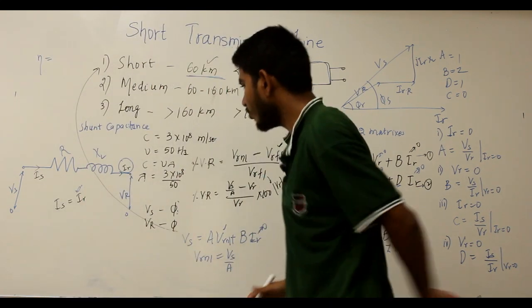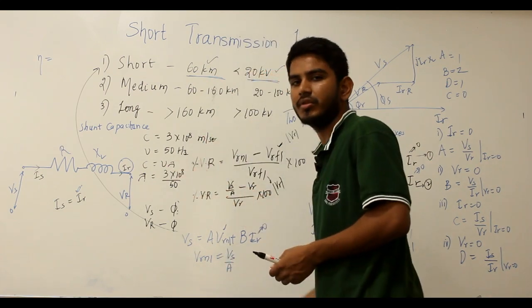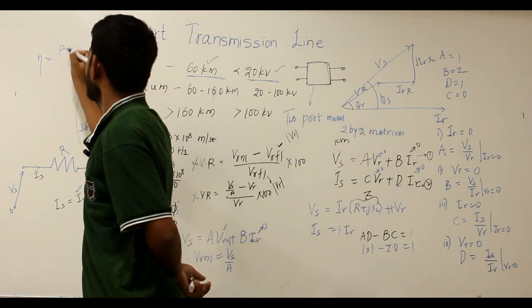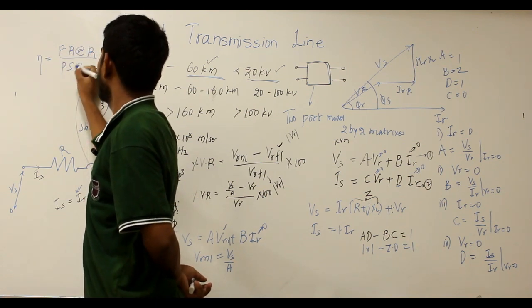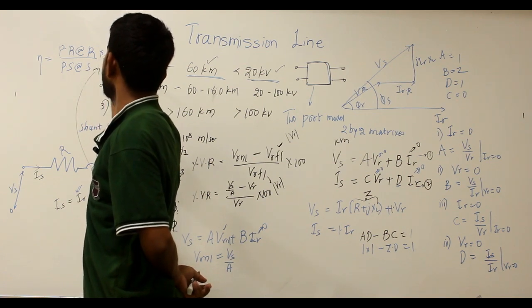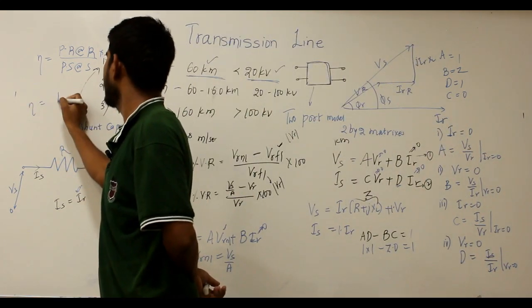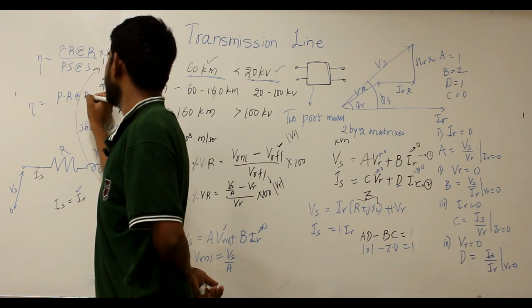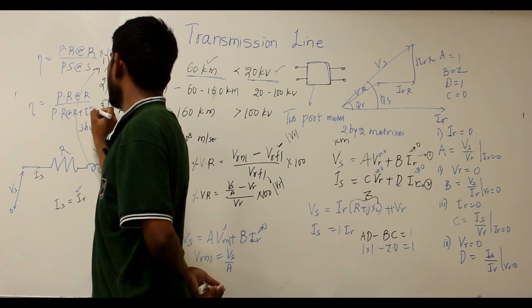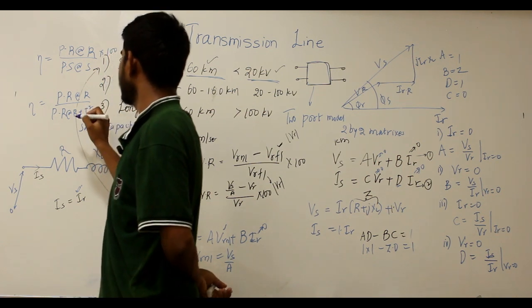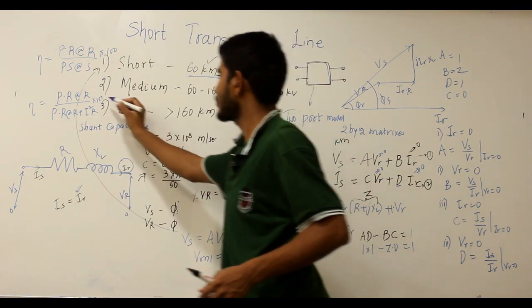The efficiency of the short transmission line is found conventionally as the power received at the receiving end divided by the power sent at the sending end, multiplied by 100. Alternatively, efficiency η = power received / (power received + I²R), where R is the equivalent resistance per phase.